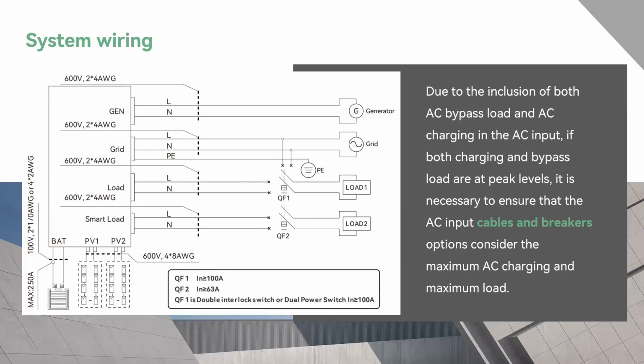Okay, so before the cable wiring, let's take a look at the system wiring again. We have stressed that when the inverter is working in the bypass mode and charging the battery at the same time, the current going through the grid side will be at maximum level. So we need to ensure that the maximum nominal current of the AC input cables and the breaker is at least 100 amperes here, for example, for the breaker one and for the grid cables here. And as for other cables, you can refer to the cable gauges here, and we also mentioned it in our user manual.